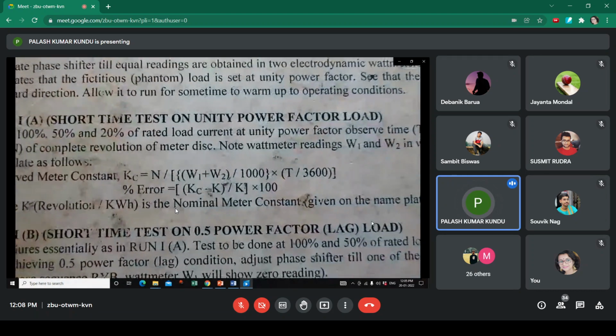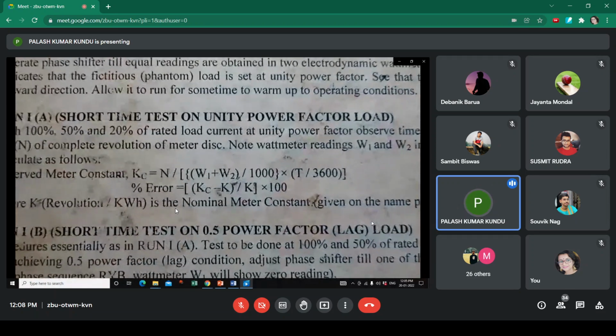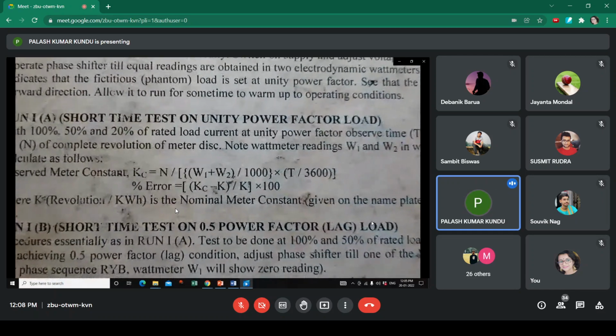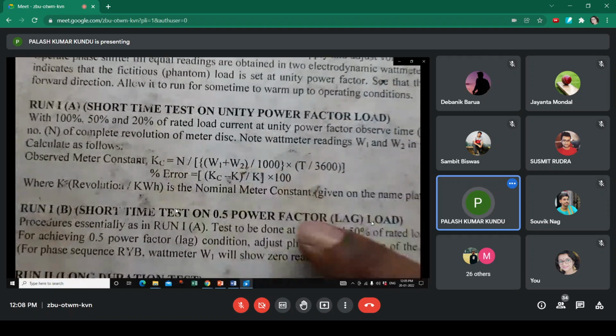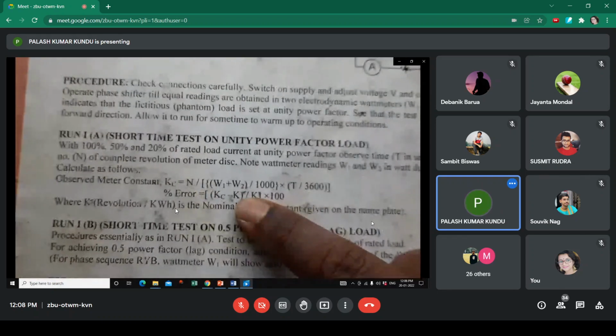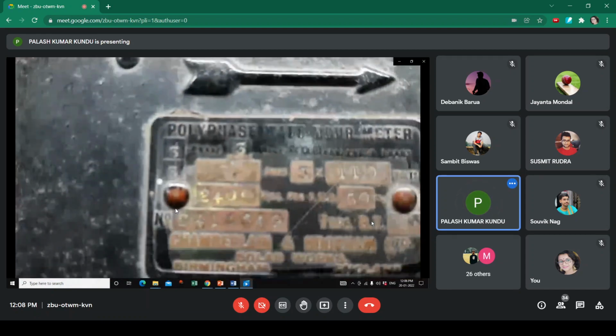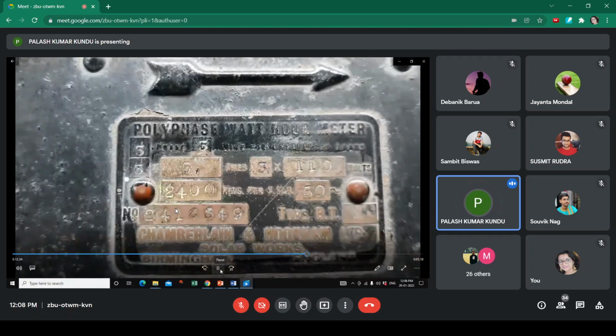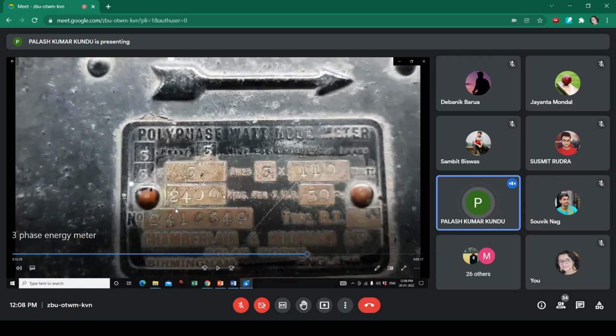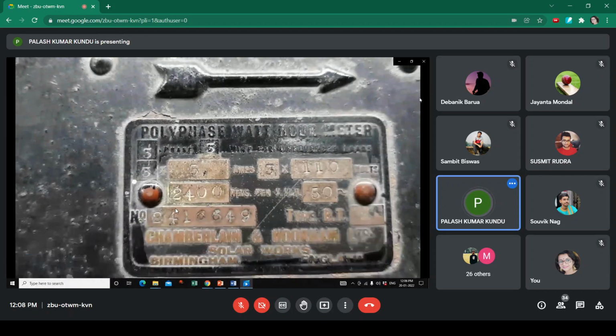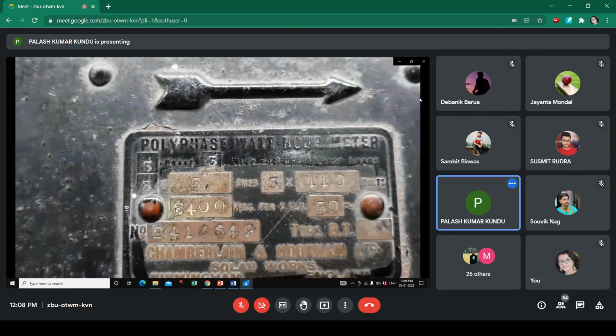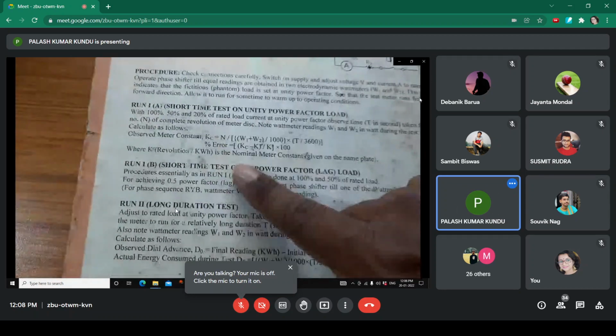When you find the percentage of error, you need to know one more value, that is K. Kc we calculate from the readings, but the value of K, the rated meter constant of this meter, you also have to know. It is written on the cover of the meter. You can see the rated meter constant specified by the manufacturer is 2400 revolutions per unit of electricity, that is 1 kilowatt hour. And you also have to find the percentage of error.